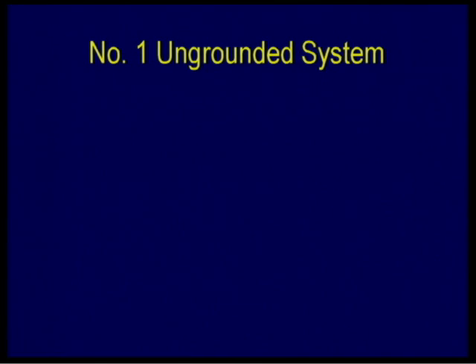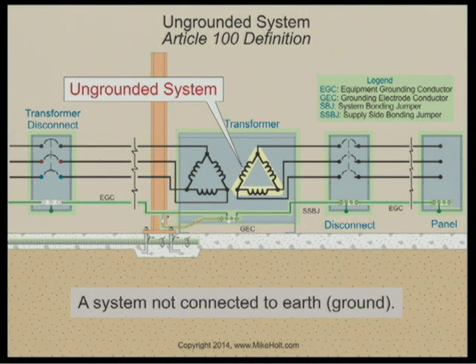Okay, let's talk about ungrounded systems. Now, the NEC defines an ungrounded system as a system not connected to the earth. If you take a look at this winding, it is shaded. That is the separately derived system. And this system has no electrical connection or conductive connection at all to anything that has a connection to the earth. So that is what we're talking about, an ungrounded system.